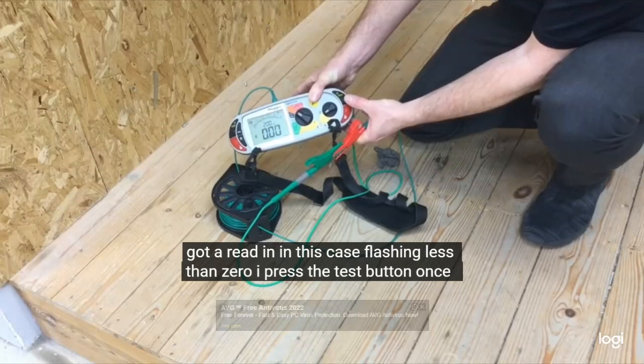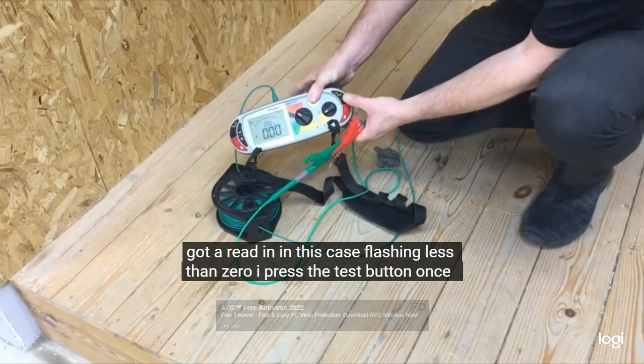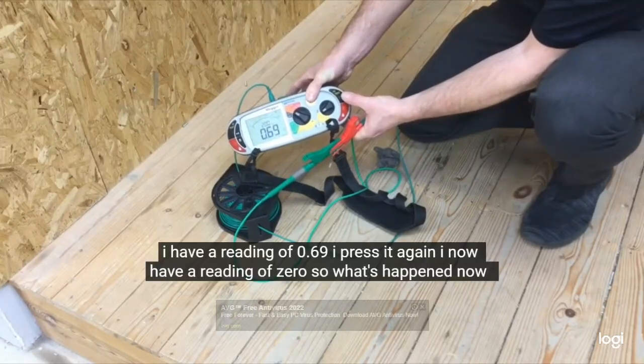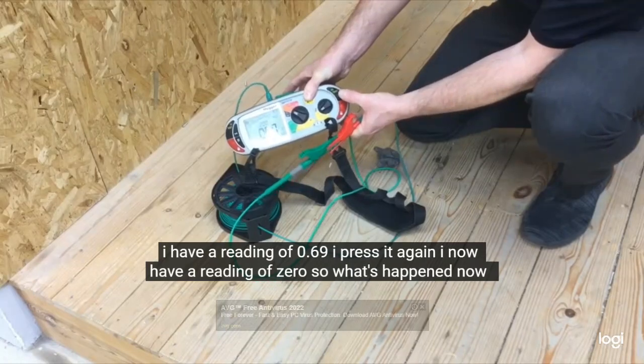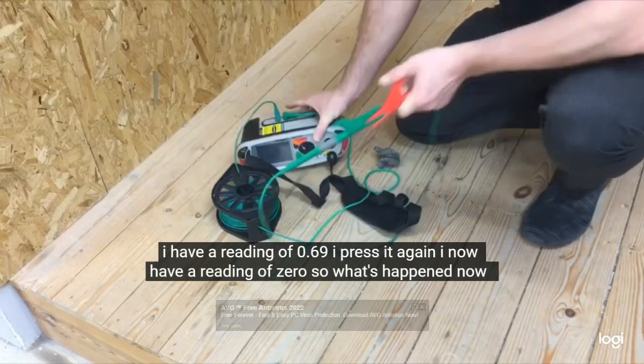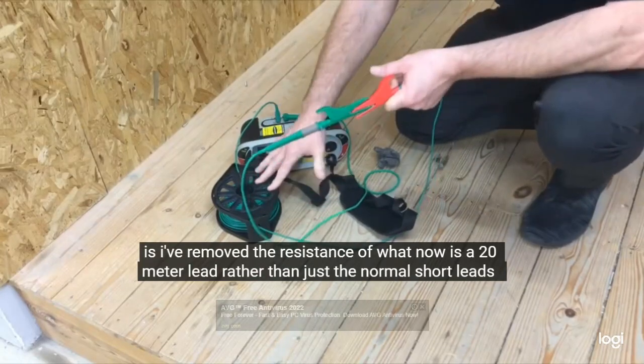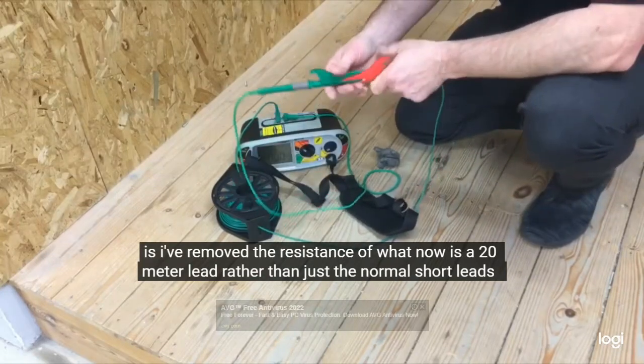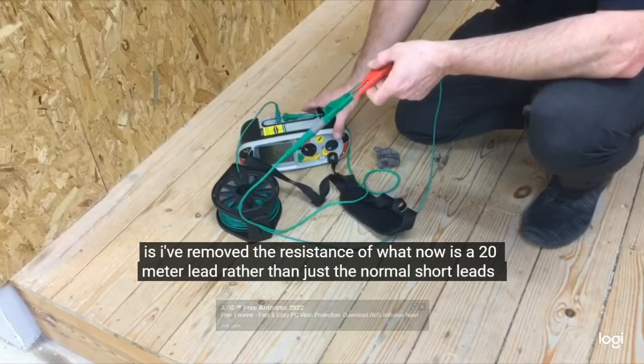I've got a reading, in this case flashing less than zero. I press the test button once, I have a reading of 0.69. I press it again, I now have a reading of zero. So what's happened now is I've removed the resistance of what is now a 20 meter lead, rather than just the normal short leads that we have on the instrument.